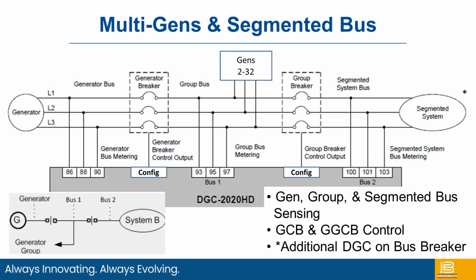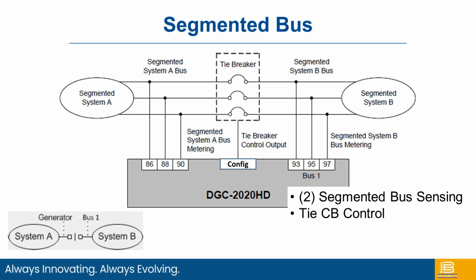Segmented bus, I mentioned earlier. This is when you have multiple generators that are tied together with a segmented bus and the group breaker, being able to control and sense. So one HD can control the generator circuit breaker, the generator group circuit breaker, and then go on to a segmented bus. And then on that segmented bus side, you can have another DGC HD that can actually control a tie breaker, which is kind of what this is illustrating. So if you remember going back a slide, we had this segmented bus A, and then we have a tie breaker. Now we're showing segmented bus B.